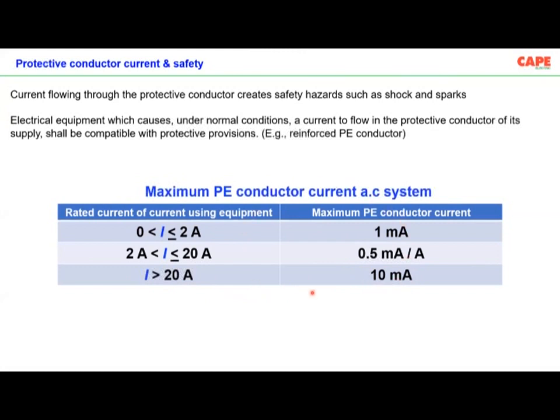This is for one condition. Probably some more conditions are there, which I am not explaining. But basically, what you should understand is that the continuous current flow through the earth wire must be negligible, very, very small. If the current flow is exceeding these limits, then we are supposed to have additional earthing provisions such as a reinforced PE conductor. In order to ensure that the current is lesser than this particular limit, every electrical installation is supposed to make a test of insulation resistance.